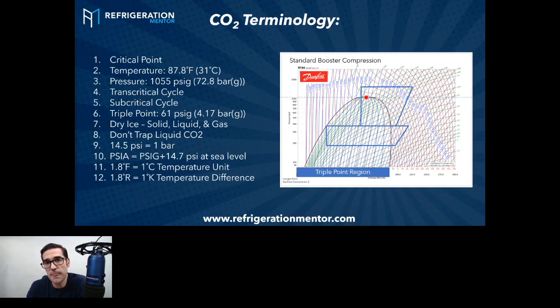You're going to get them and just have to hook up your water supply, for example. But when you get to a larger system, a larger heat pump, you'll be actually charging that system. Or if you had a leak on the system and had to do a repair, there are certain steps you need to take to charge that system. And we'll talk about that in a little bit. You don't want to trap CO2 unless you have the proper equipment. A lot of the heat pumps that you will work on have high standstill pressures, and really what that means is they can handle the pressures, so they don't blow any reliefs.